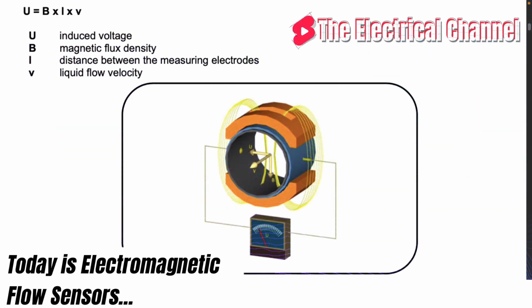The function of an induction flow meter is based on Faraday's induction law. The meter sensor consists of a non-magnetic and non-conductive tube with two embedded measuring electrodes to pick up the induced voltage. To create an alternating magnetic field, two coils are fitted into the tube in parallel with the plane defined by active parts of the measuring electrodes.